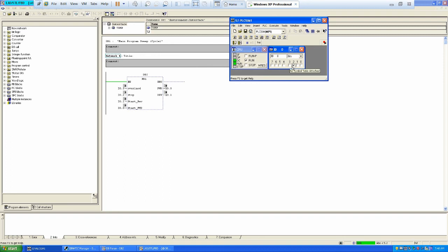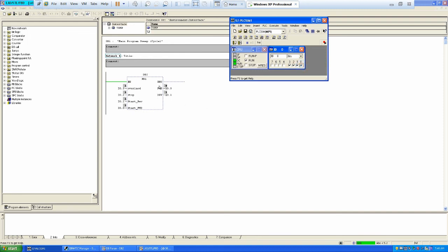We will select I0.2 and I0.3 — because these are in normally closed configuration in the field. Now after that, if we press the start button for forward, you can see the motor is running in the forward direction. And if we press start reverse — motor is running in the reverse direction. But when the motor is running in the reverse direction, if you try to press in the forward direction, it is not going to run because we have defined the interlock. So it's going to continue running in reverse. If I press I0.0 that's for forward running, you can see the motor is still running in the reverse direction — it's not caring about that command to run in the forward direction.